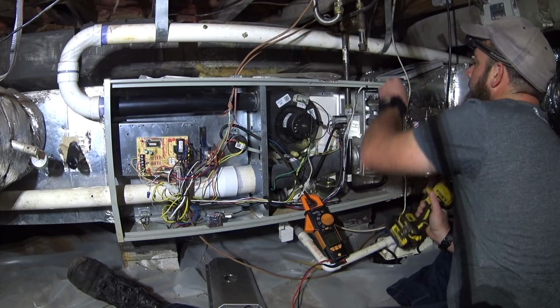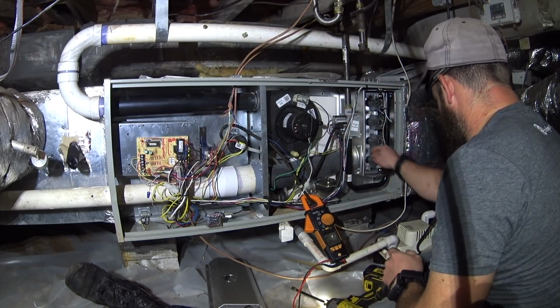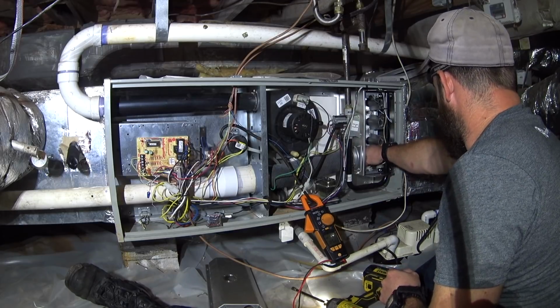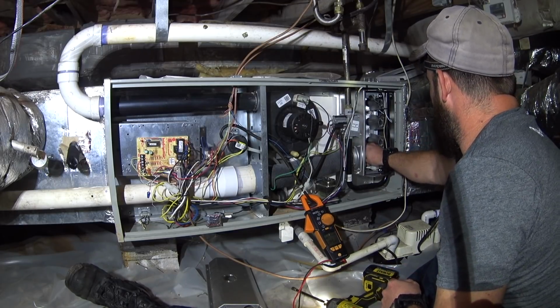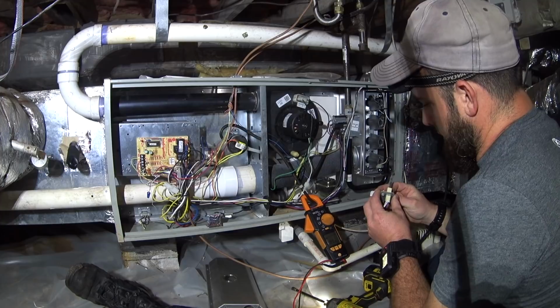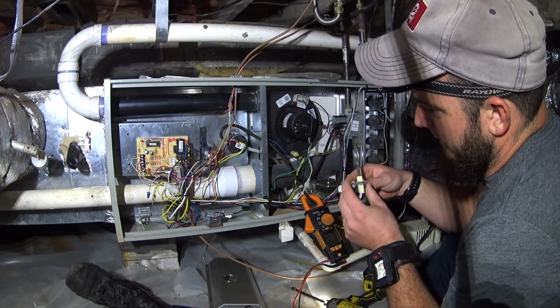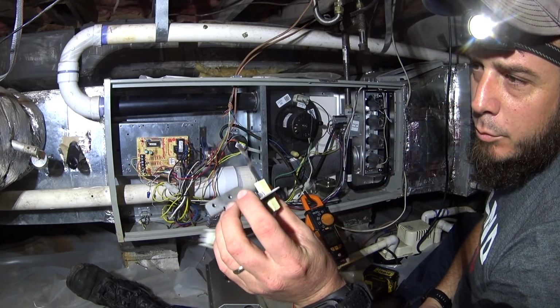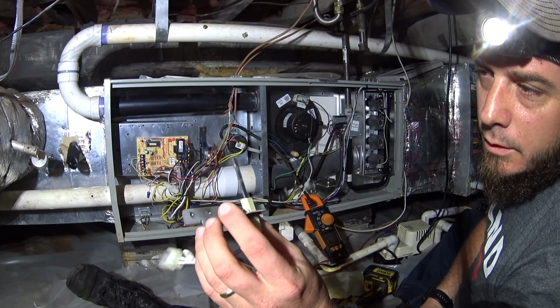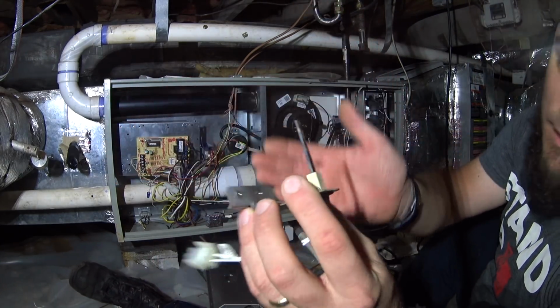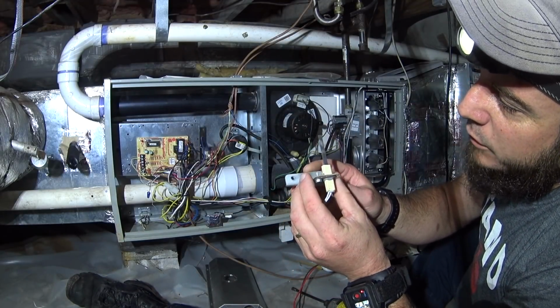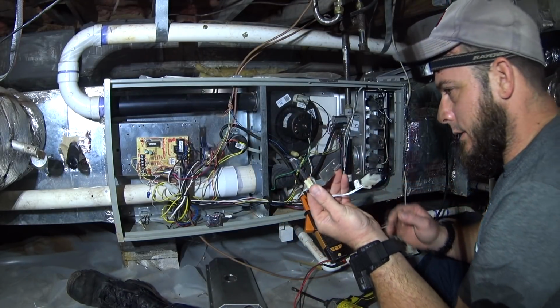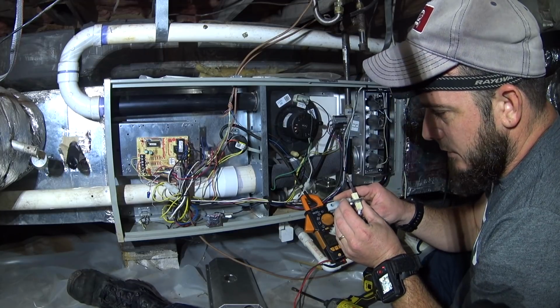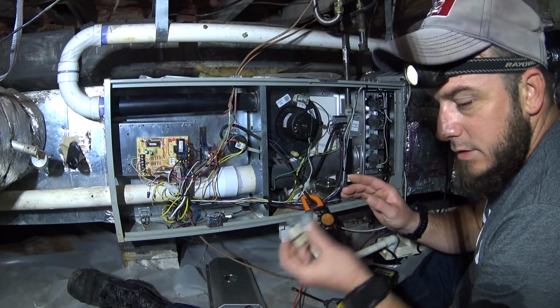I always have to clean the burners, and if I'm going to have to clean the burners anyway, I'm going to have to disassemble and look at the burners and the heat exchanger from the burner access. Don't think you can see that very well, but it has some buildup on it, but not so much that I'm concerned with its expected longevity.